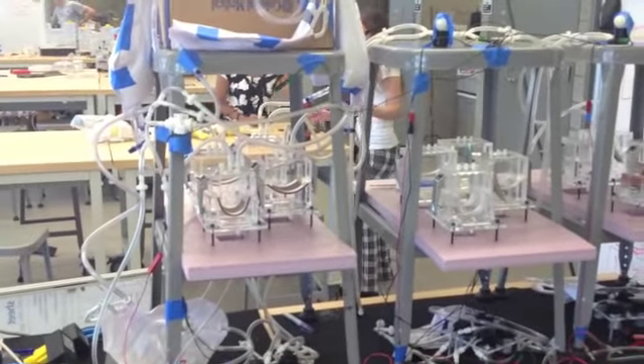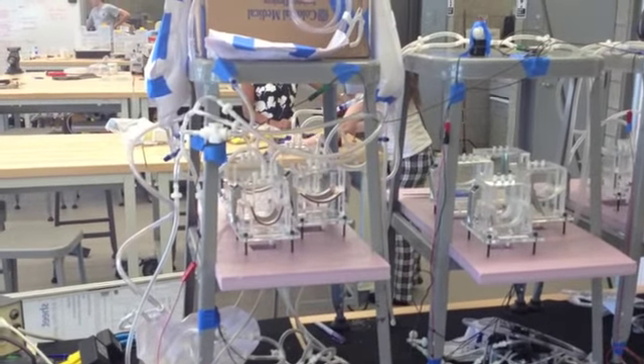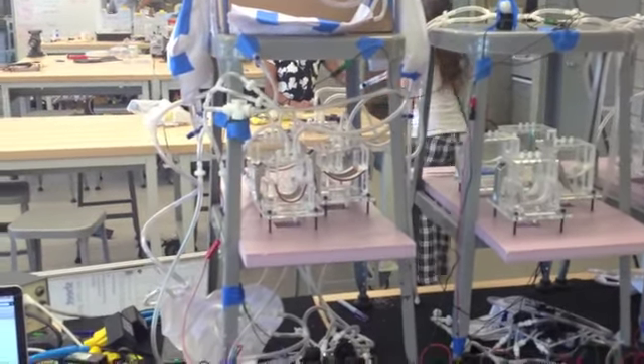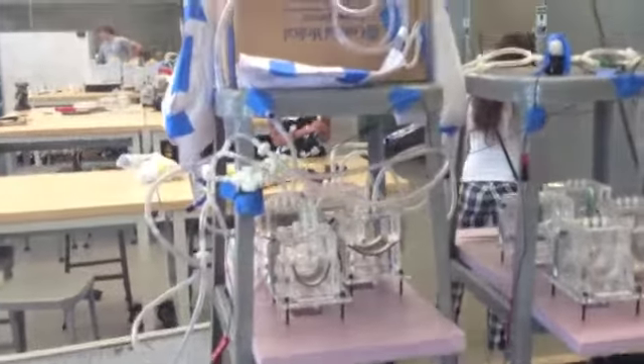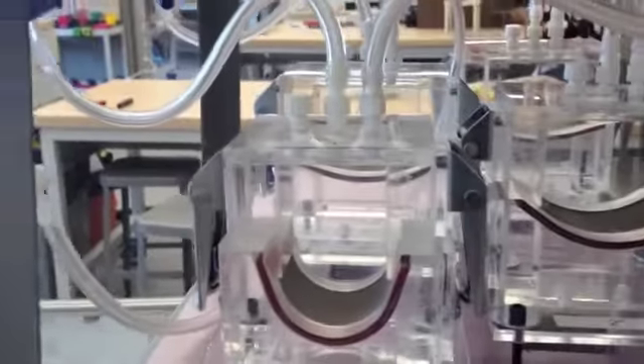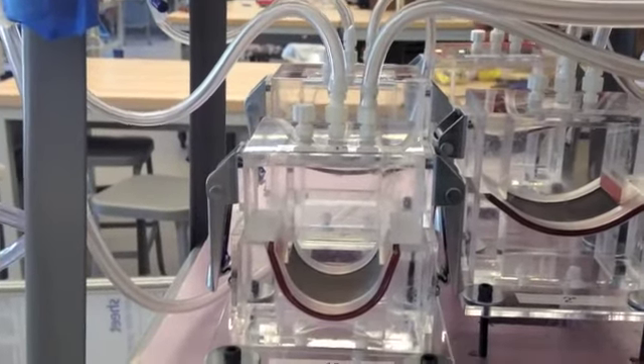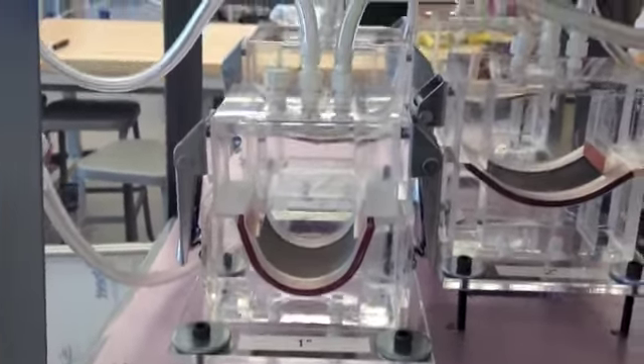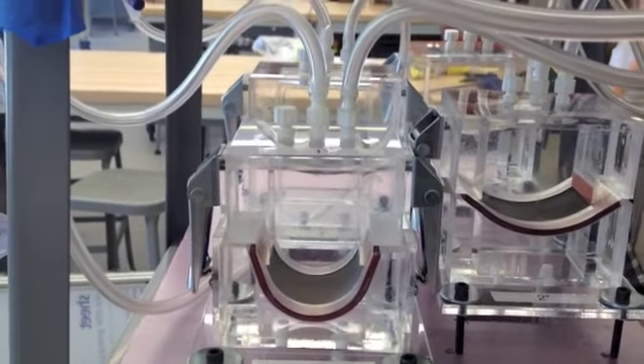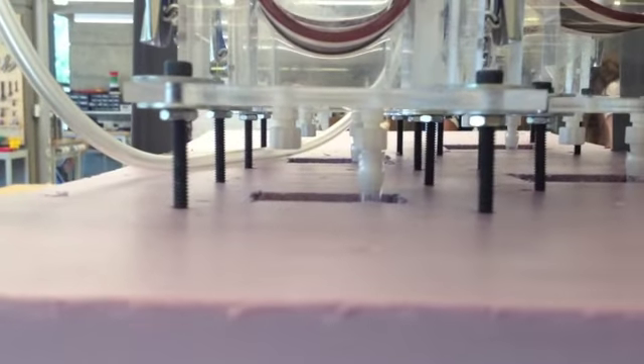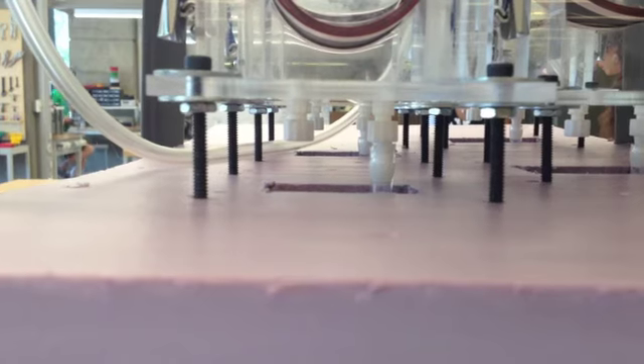Okay, so let's see here. The way the tubing works is that we have a nice layout of it, which I can maybe show you guys a picture of, but the basic idea is that in the top of the cell, one port is for refilling, which is the middle one. The right port on the top of the number 1 cell here is for venting, and the left one is for the transducers, which we don't have hooked up right now. And then in the bottom, the right one is for pressurizing, venting, and draining, and the left one is for the transducer. So currently we don't have the transducers in because our printed circuit boards aren't in yet, so we just have all those ends capped.